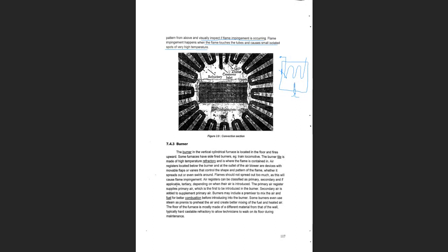اللهب ما يكون طويل جدا، لانه if it is too long يا شباب because of the high pressure as an example the flame will elongate، راح يطول الين يصل الى درجه يبدا يلمس ايش؟ يلمس التيوب. واذا لمس التيوب هنا يا اخوان you will have the spot here يا شباب at which the flame is touching the coil will be exposed to extremely high temperature. Or in other words you will have what is known as the hot spot.